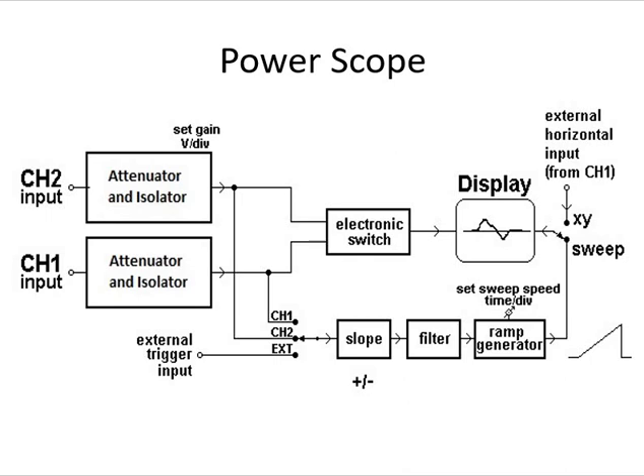A normal oscilloscope has two input terminals: main and ground, where the ground terminal is always at zero potential. The power scope is used to observe waveforms of a signal in any branch of a circuit, even if none of the terminals of that branch are connected to ground. It is also used for high voltage circuits to observe high amplitude waveforms. The power scope is similar to a normal oscilloscope except in its input circuit, which consists of an attenuator and isolator.